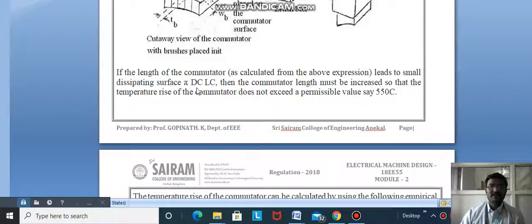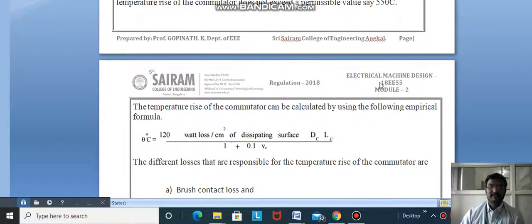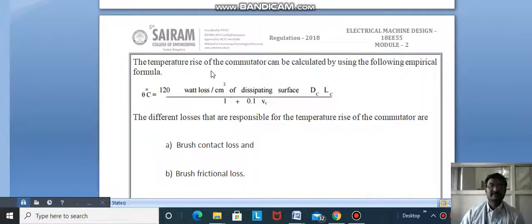If the length of commutator as calculated from the above expression leads to small dissipating surface π Dc Lc, then the commutator length must be increased so that the temperature rise does not exceed a permissible value, say 55°C.